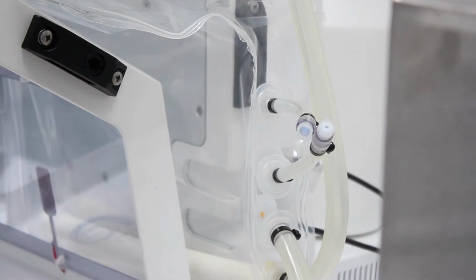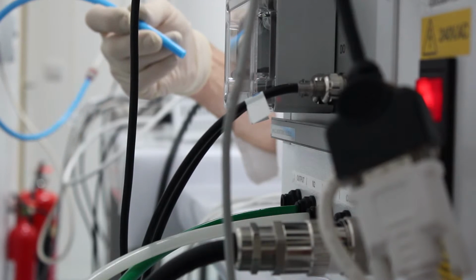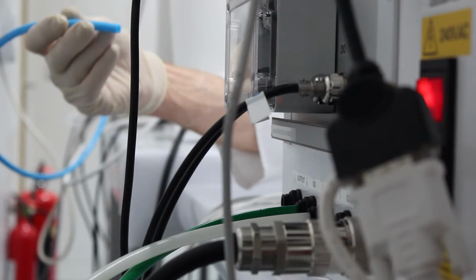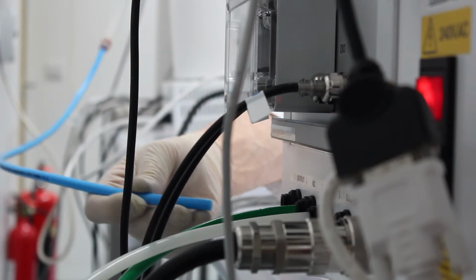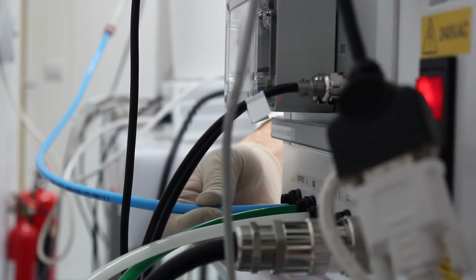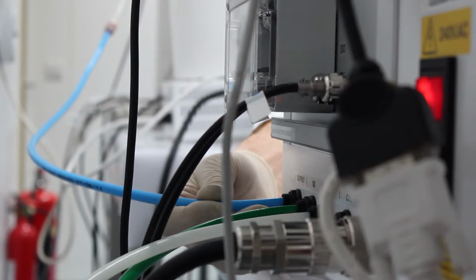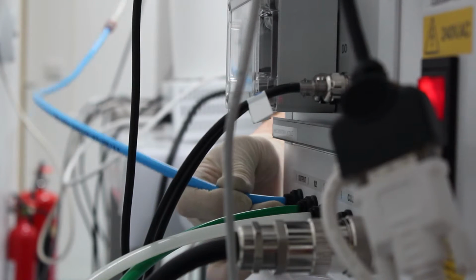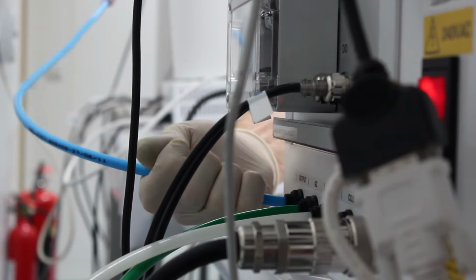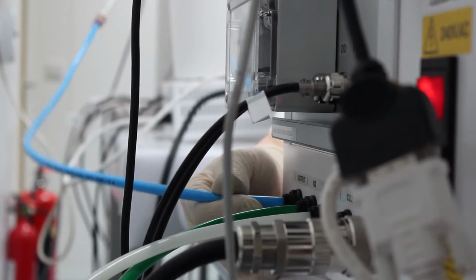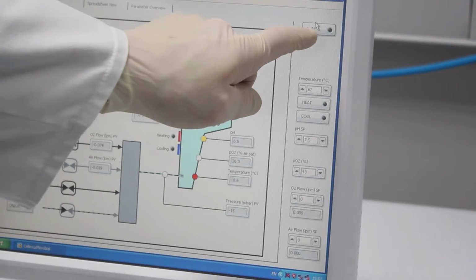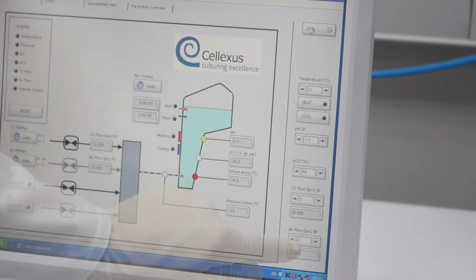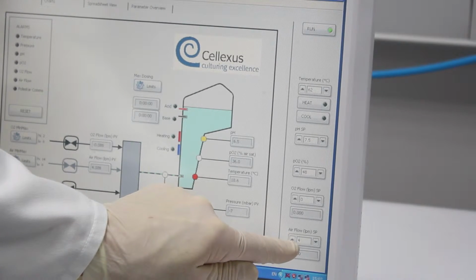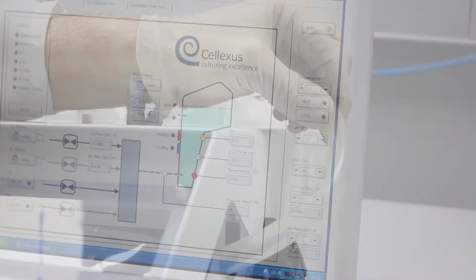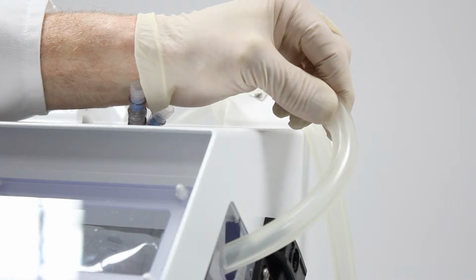Fibre optic probes permit reading from the probe patches attached to the ports at the back of the Cellmaker bag, and signal is delivered to a reader device housed in the controller, which converts the signal and permits control via a feedback loop. The Cellmaker bag is first filled with air to prevent creasing of the Cellmaker bag during installation and facilitates the best fit of the Cellmaker bag into the Cellmaker enclosure.